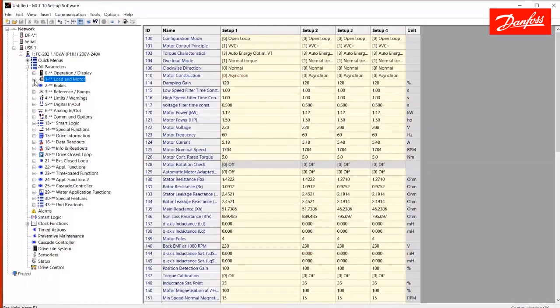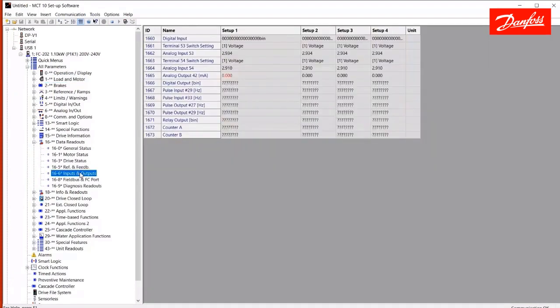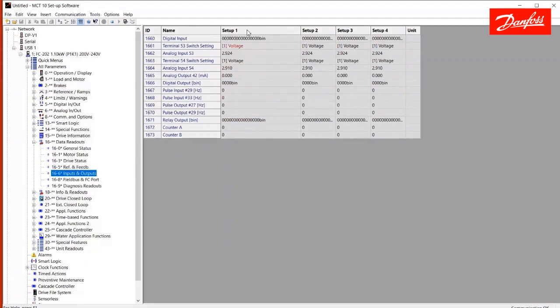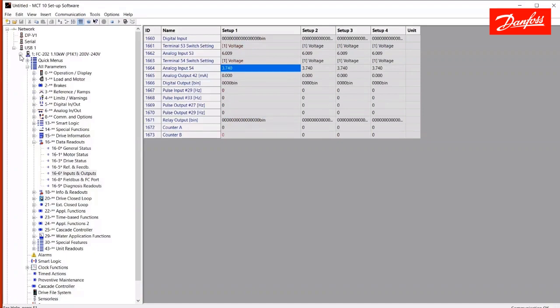Also, for example, if I go down to group 16 data readouts, an area where you can read back data from the drive. It's a read only group. I'll select inputs and outputs here. And just to display this, and we can see again that there's a live connection. The connected drive, I also have an IO simulator box connected to. So I can manipulate values. So I'm going to change the voltage on analog 53. And we should see that being reflected here. Again, so we do have a live connection to this drive. When I read and write, it's done on the fly.